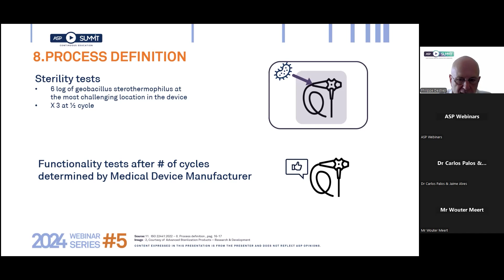So the top of the next slide illustrates what I said before about the requirement for the sterility test, that is to say, placing germs at the most difficult location in the device and performing tests at half cycle to reach the 10 to the minus 6 sterility assurance level. What needs to be remembered from the former slide is that sterilization processes or mechanisms are extremely complex. To make a long story short, it's difficult to model them and to avoid tests on real medical devices.